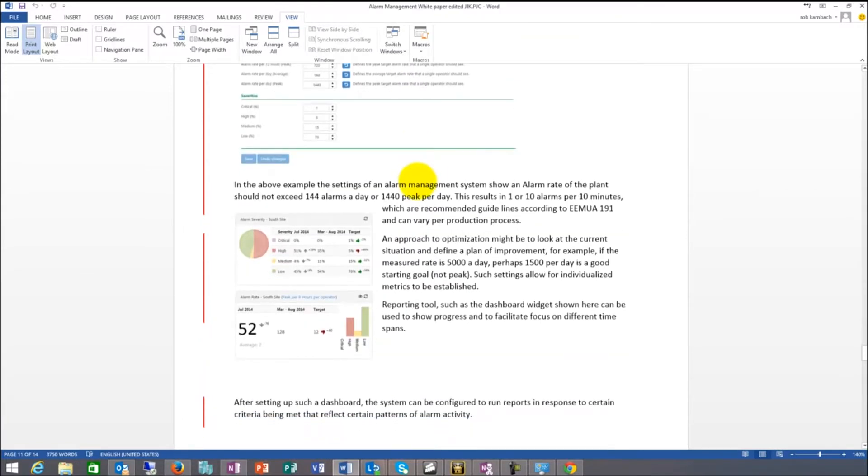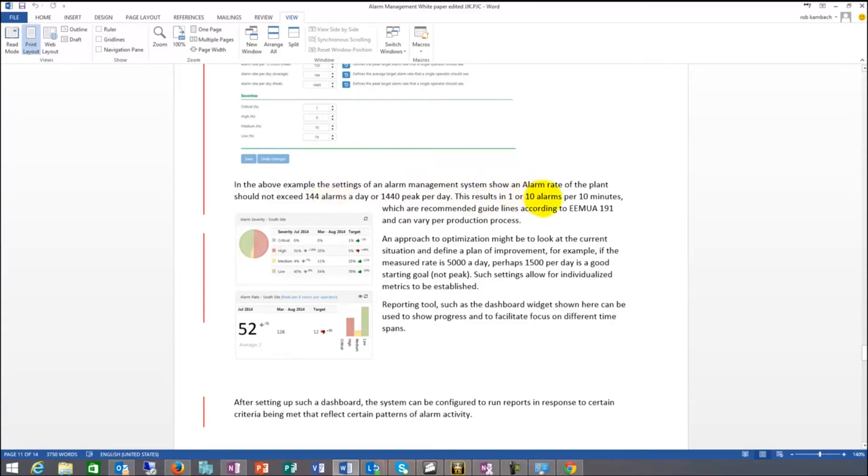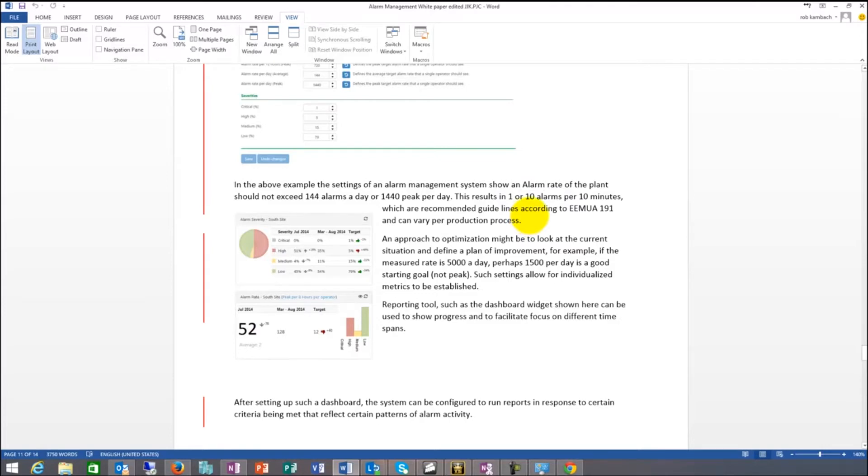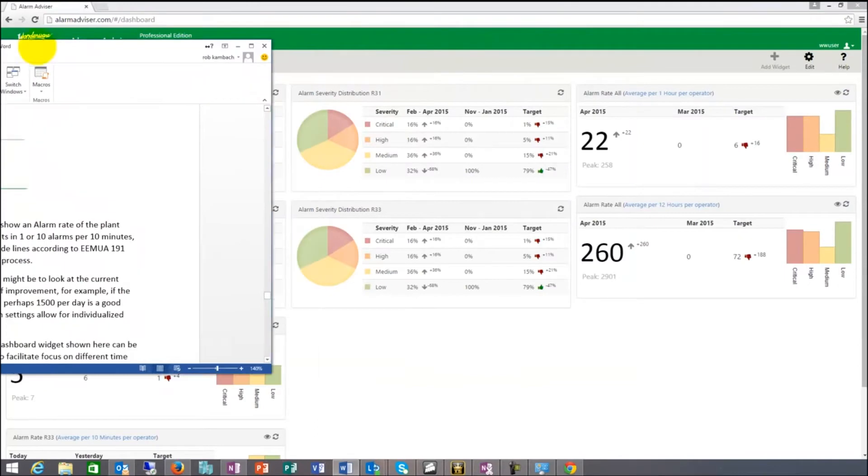If you look at the EEMUA, there are 1440 alarms peak per day or 144 alarms a day in regular mode. One to 10 alarms per 10 minutes. One alarm is average, 10 alarms is peak, which are recommended guidelines according to the EEMUA. But they can vary by process and by location.